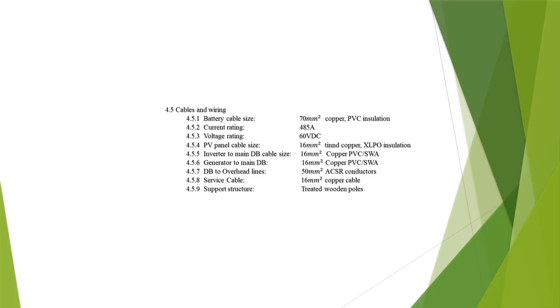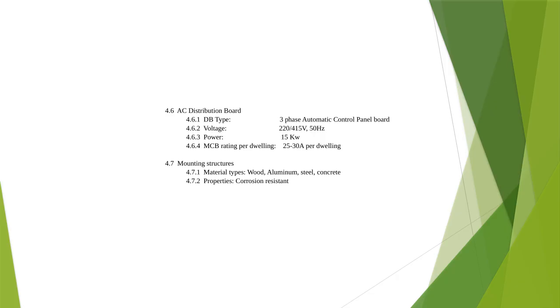And from DB to overhead lines, we use 50 square millimeter ACSR conductors, and the service cable should be 16 square millimeter copper cable, and the support structure for overhead lines to be treated wooden poles. And then from AC DB, the DB type to be a 3-phase automatic control panel board. Operating voltage for this DB to be 220 or 415 volts, 50 hertz, with a maximum power of 15 kilowatts, and MCB rating per dwelling should be 25 to 30 amp per dwelling. And on mounting structures, the material types that are going to be used are wood, aluminum, steel, and concrete. And these mounting structures must be corrosion resistant.